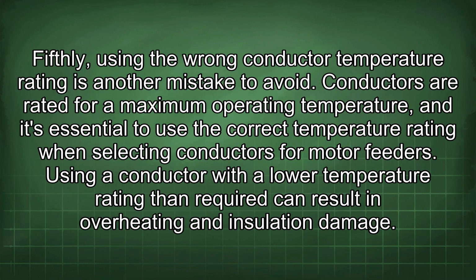Fifthly, using the wrong conductor temperature rating is another mistake to avoid. Conductors are rated for a maximum operating temperature, and it's essential to use the correct temperature rating when selecting conductors for motor feeders. Using a conductor with a lower temperature rating than required can result in overheating and insulation damage.